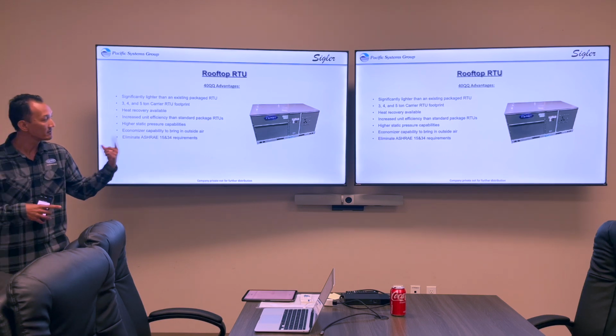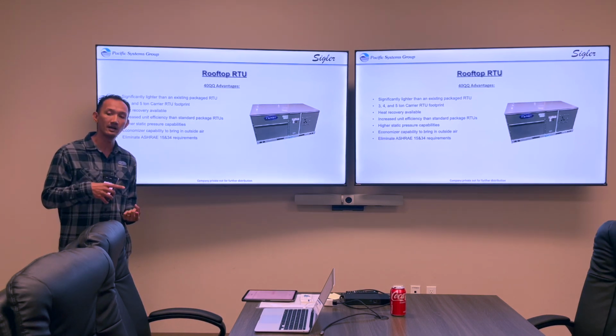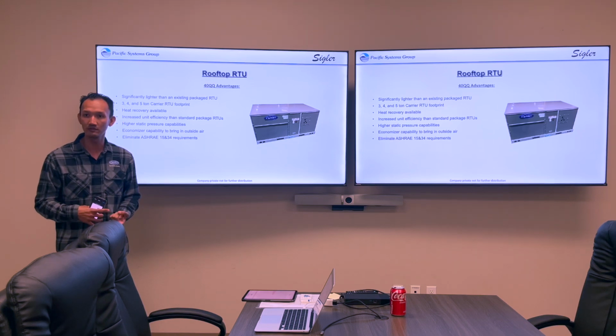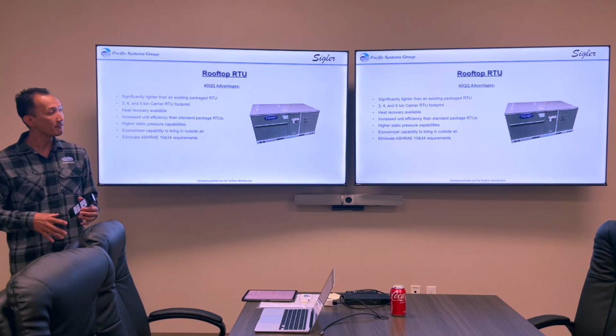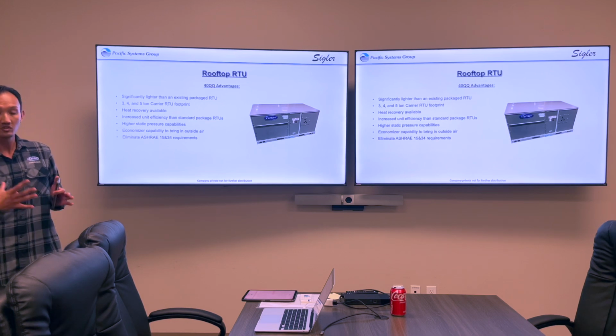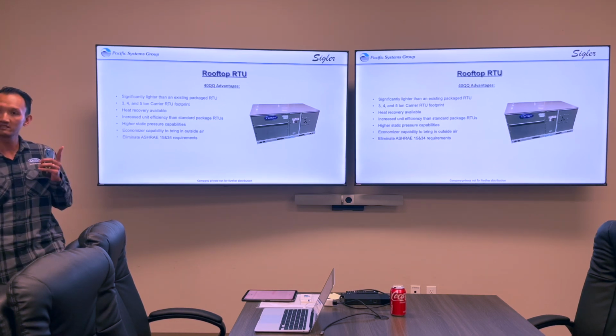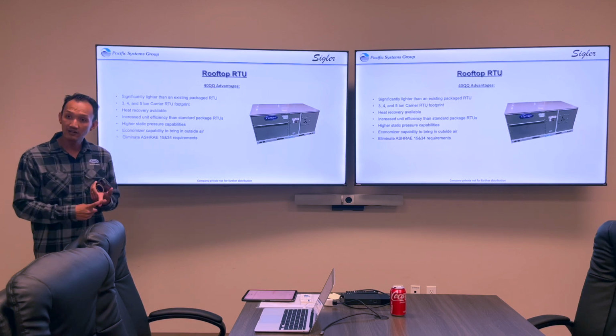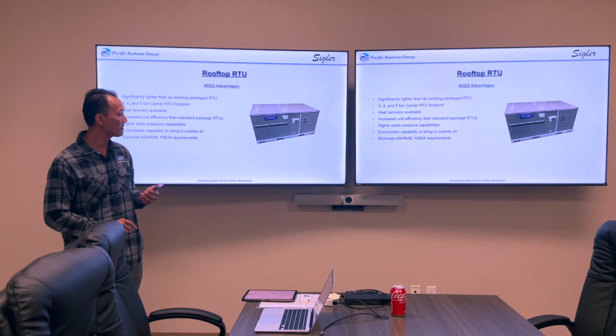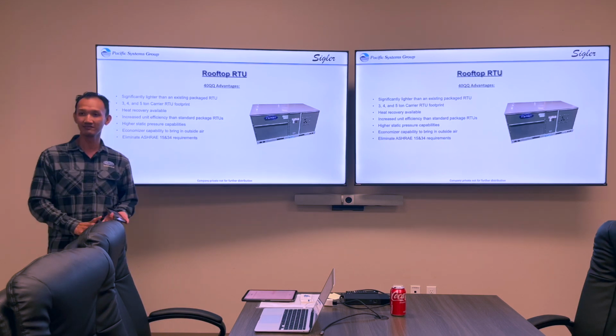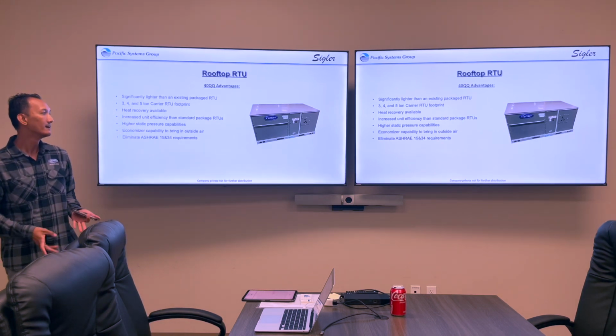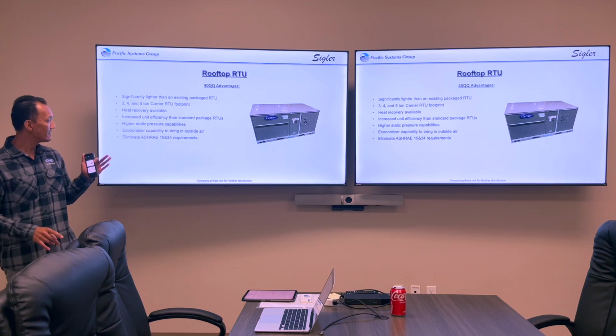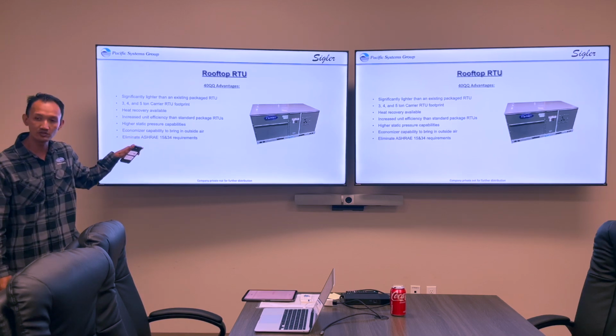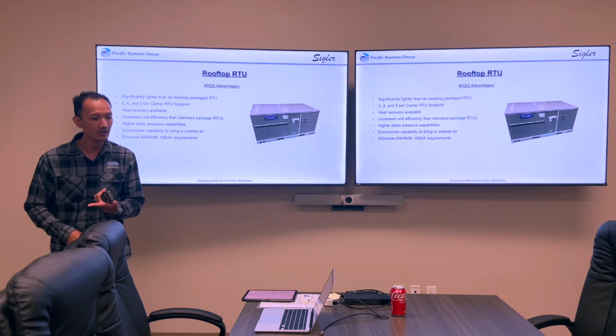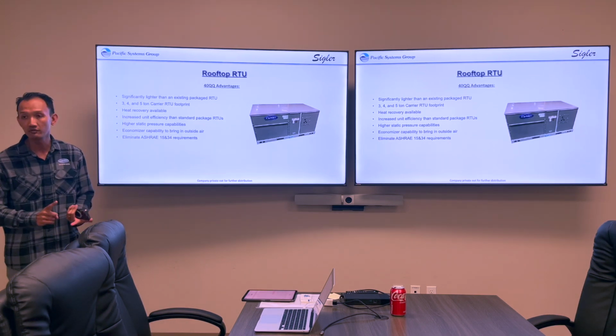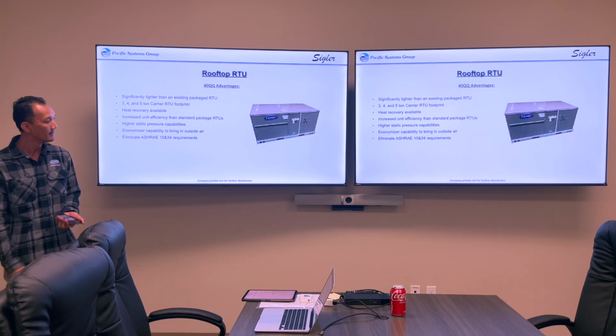One of the great things about these is that since it uses the existing Carrier rooftop, it's the same footprint that Carrier has been using for decades now. So if you have existing rooftops, you can just take those off. You can use the existing roof curb. You can use the existing ductwork. They're a lot lighter than the existing rooftops because half the rooftop is gone, right? There's no compressor, no condenser equipment, and then you can use a lot of the same accessories as a Carrier rooftop. So economizer for ventilation or using free cooling when conditions allow for it.